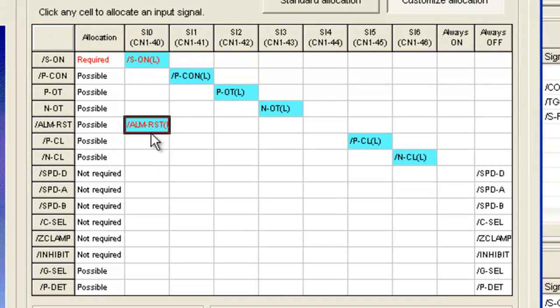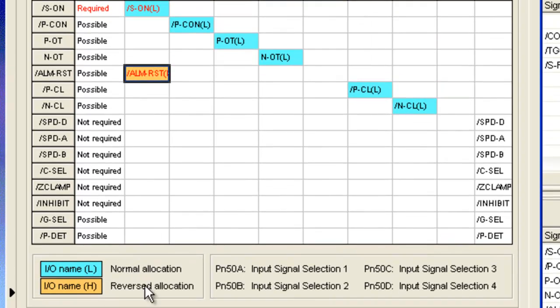You notice that is somewhat of a warning here. They turned the text red. But then not only that, I can click on it again, and that reverses the allocation, meaning instead of normally open, it's normally closed. And so now when I open the connection to pin 40, I'll reset an alarm. And when I close the connection to pin 40, I'll turn the servo on.